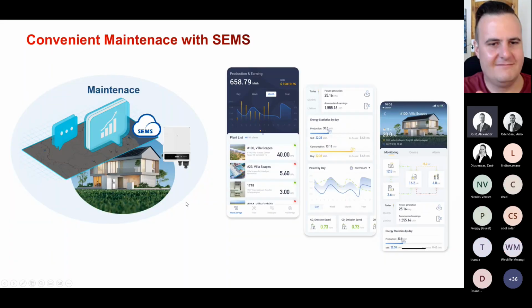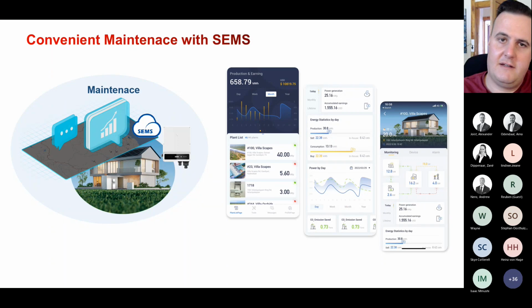David, thanks so much. Can we talk about the paralleling capability of the ET units? Yeah, so the ET units will parallel at some stage. I don't have an exact timeline for that. We do have a new controller being released for these parallel systems. For the three-phase systems, even our on-grid inverters, there's a new device coming, I think due around August. Once that's available, we'll get confirmation of the paralleling of these inverters and how that parallel will work. So currently we just have to work off the assumption that they do not parallel at the moment. Once that new communication device has been released, then we can introduce the parallel of that system.